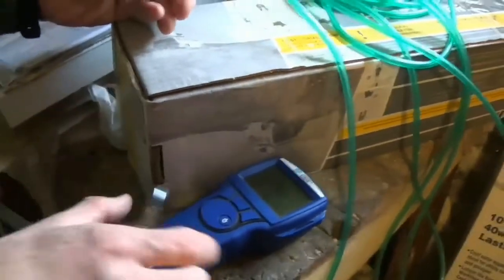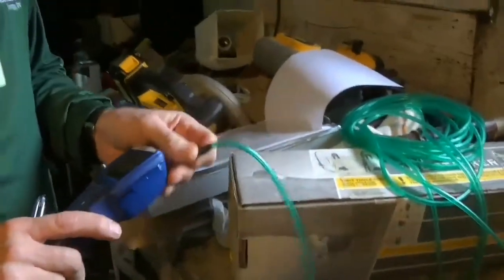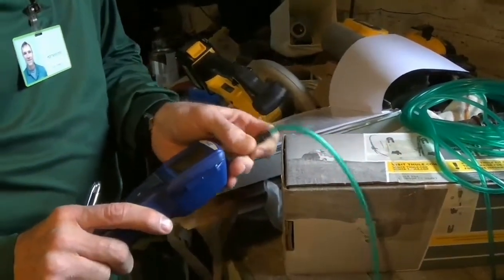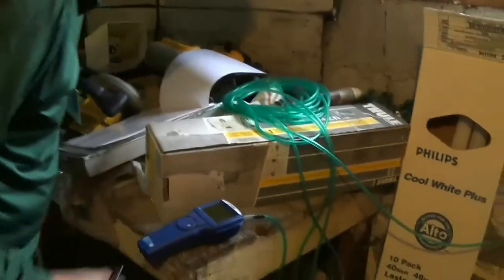So now I got a 0, so now I'm going to go ahead and hook up my hose. And what I'm getting here by going on the right hand side is I'm leaving the reference open to the room that I'm in, and I'm getting the pressure in the combustion appliance zone with reference to outside. And so I'm looking at a number that's a lot different than 0, and it is a negative number.